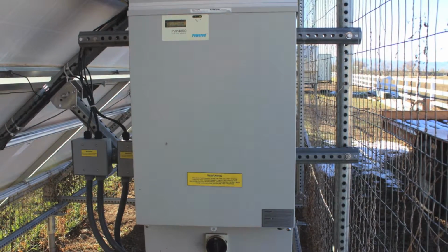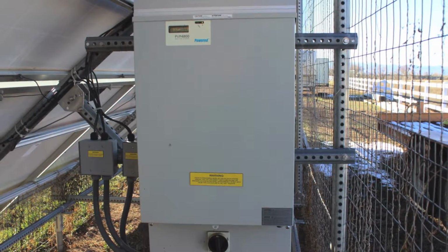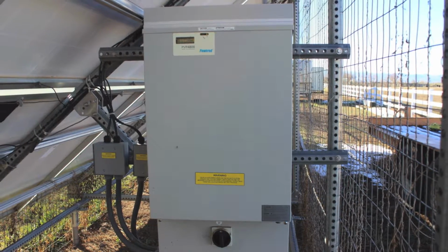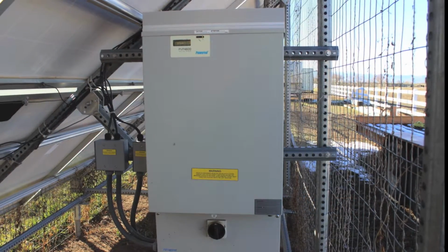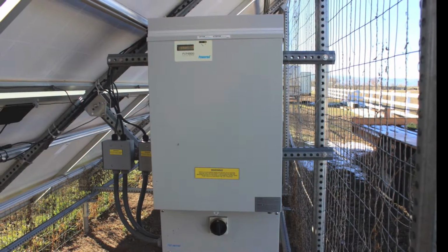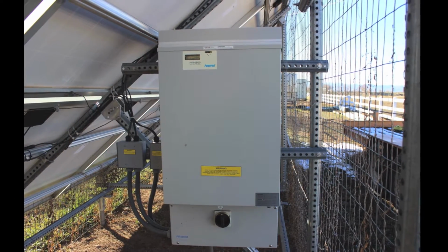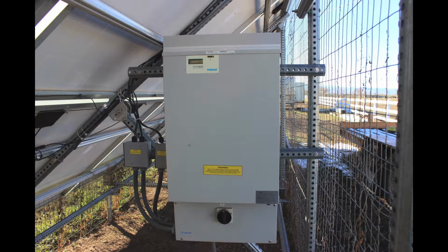This conversion takes place at a programmable inverter that receives all power generated by the panels and turns it into alternating current. It modulates this current to match the profile of the power grid and also monitors the array's overall production. The inverter shown here is known as a string inverter, which is to say that it accepts the power of multiple panels wired together in a series configuration referred to as a string. An inverter is usually never far from the panels, and in this example, it is mounted to the same racking that the panels themselves are.